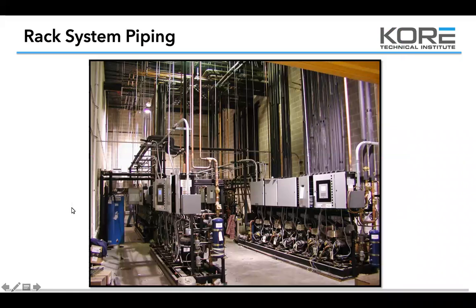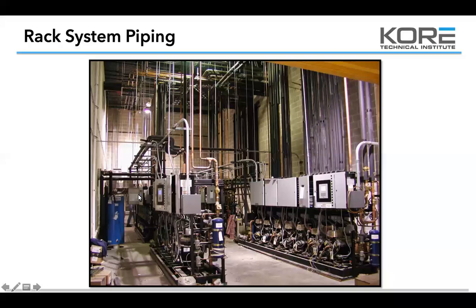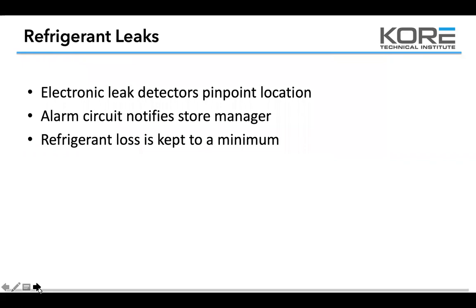This looks like a nightmare, but this is about a 10-compressor rack system, with multiple racks in the machine room and all your refrigerant lines going up and heading out to the cases. You see your rack controllers on the front. There's also a Thermostore here — a heat reclaim hot water recovery tank — another way to maximize heat gain. As we pick heat up from the cases, we send it through this tank, transfer that heat to the water, then send it back out to the condenser to condense the rest, then down to the receiver.